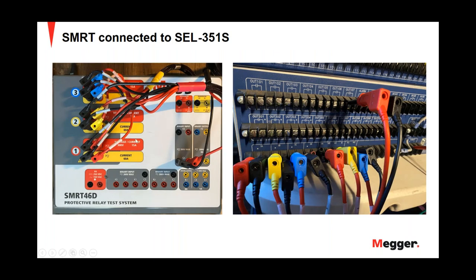Here's what the test set looks like. I have the 46D sitting here with all my test leads coming out of the top — red cables for my voltages and yellow cable for my currents. On the back, polarity and non-polarity connections all the way down. Then voltage for A, B, and C, and also binary input. I'm using output 107 for this test, which connects down to binary input number one — that will be important when we're walking through these tests.